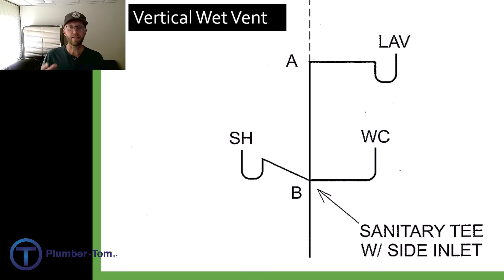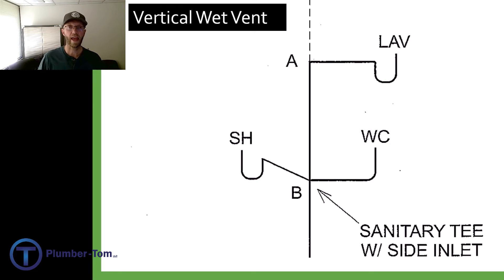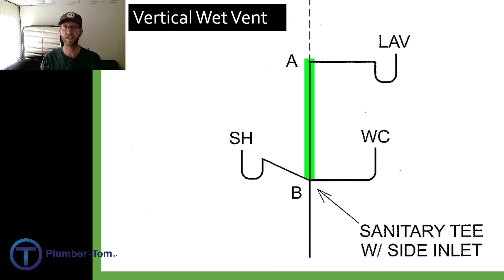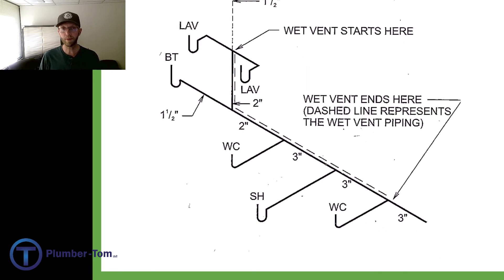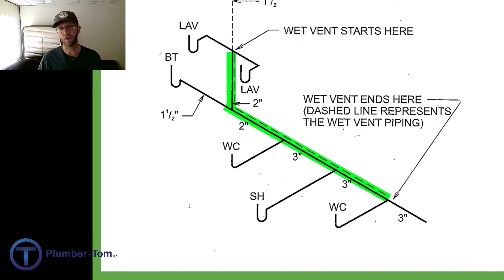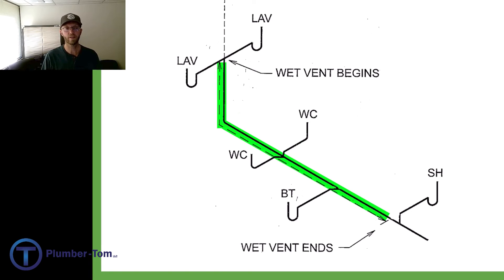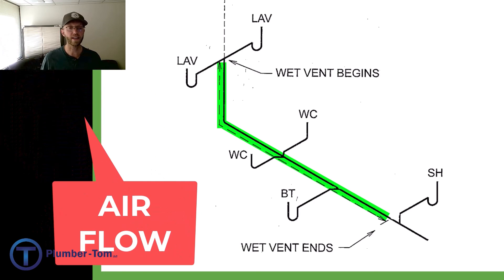Here's an example of a vertical wet vent. A vertical wet vent is just a stack but with the same principle. The stack is coming up, it branches off to the right for the toilet, to the left for the shower, and at the top we have the lav. The lav has a vent and all of the pipe from point A to B is both a drain for the lav and a vent for the other fixtures. The key principle is that when we are wet venting, it is the drain that is also a vent, and that extends all the way down to the last fixture in that wet vent system. That perforated line represents both the drain and the vent as airflow is provided to all of those fixtures.